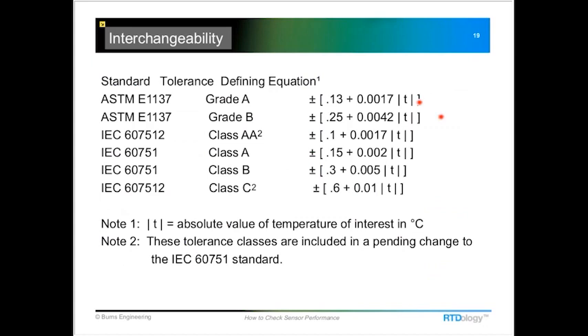And we can use these equations to actually calculate the interchangeability at any given temperature. So if we know that we purchased, let's say, this Grade A sensor, we can plug in the temperature of interest here, and it's the absolute value of temperature. So if it's a negative temperature, you would just drop the negative sign. Do the math, and it'll tell you what the interchangeability is at that particular temperature. For 0 degrees C, of course, this part of the equation drops off, and we just have this plus or minus 0.13. So if we were checking a Grade A RTD in the ice bath, we'd want to make sure that we hit that plus or minus 0.13. If it's outside of that range, it means the probe has drifted, or something else has happened to it. It got dropped, or you should consider replacing it at that point.